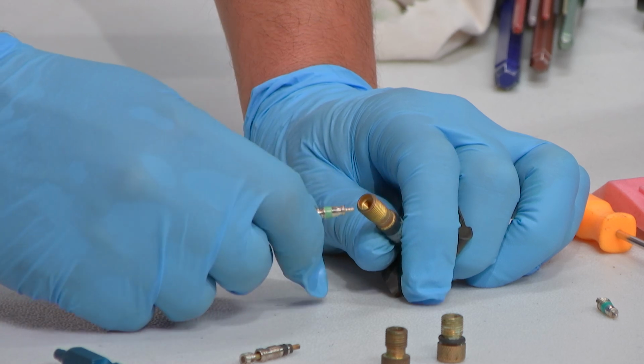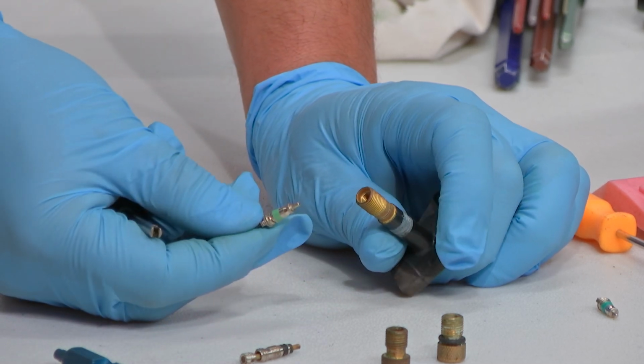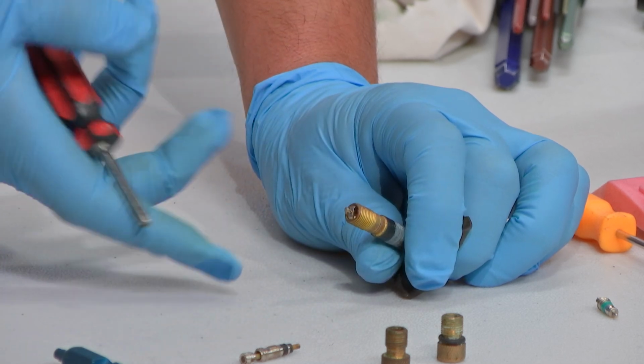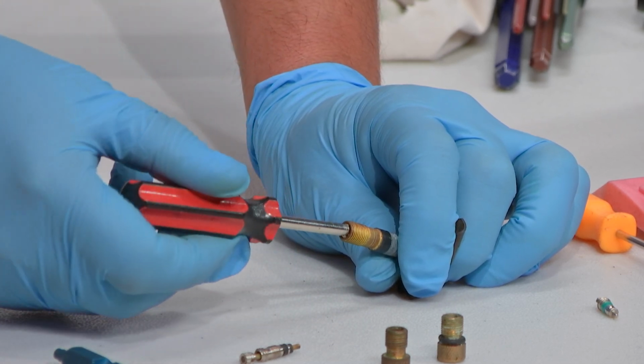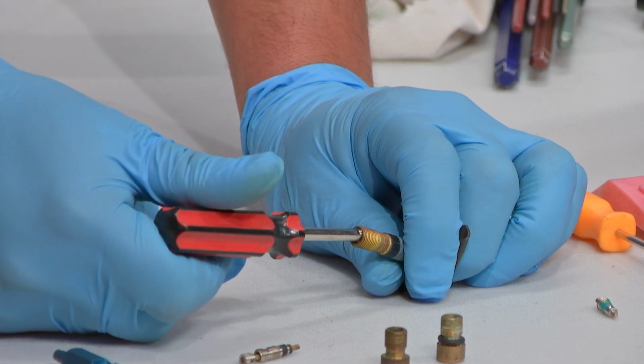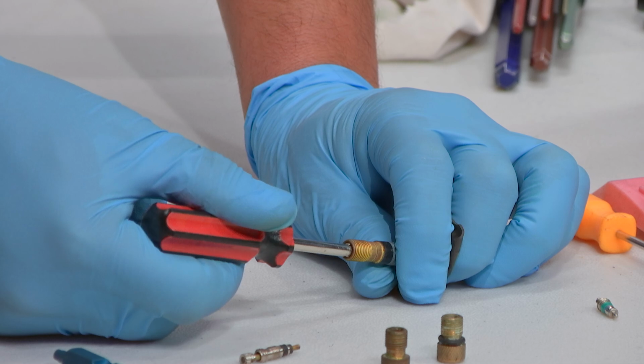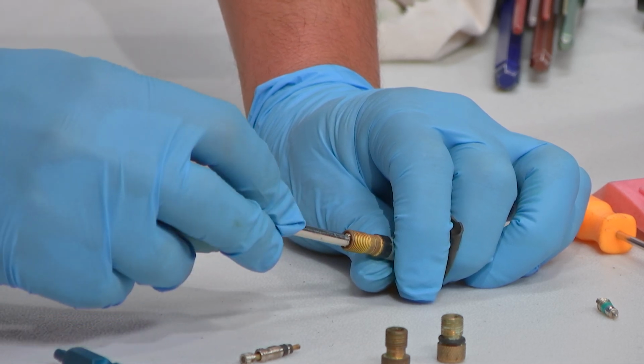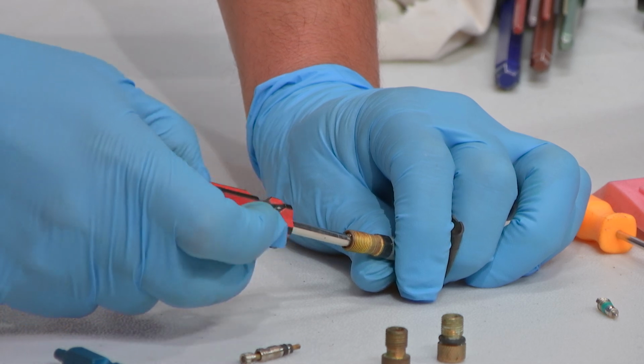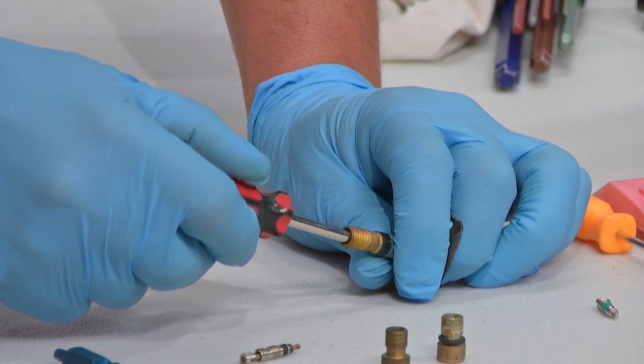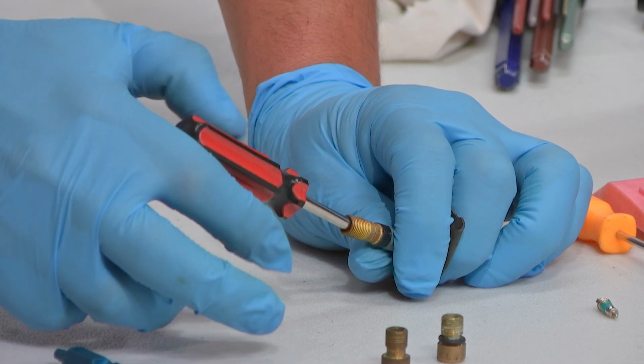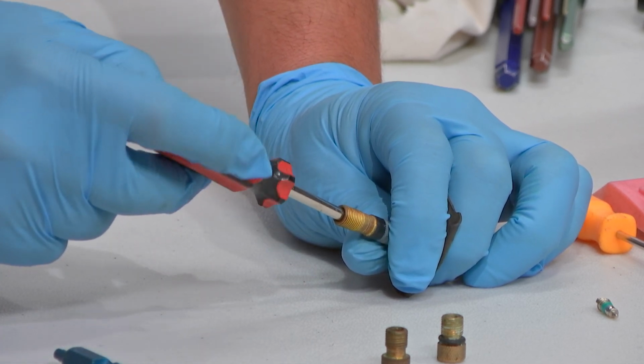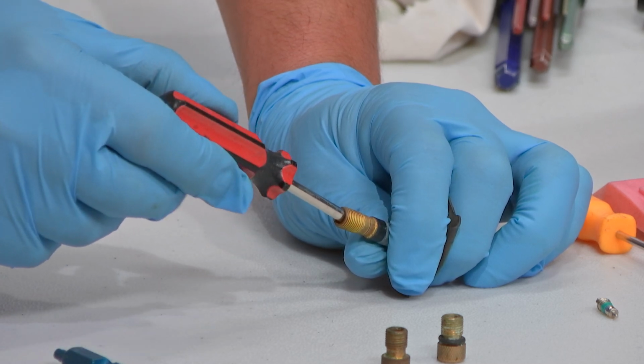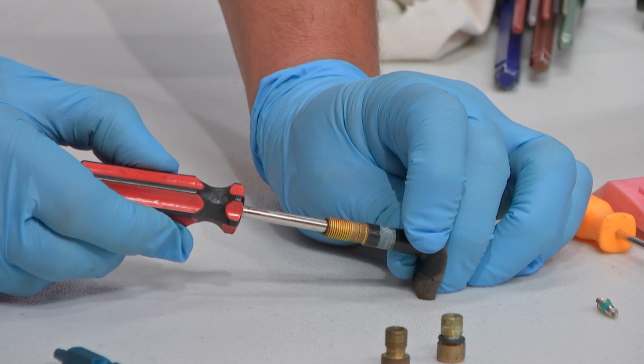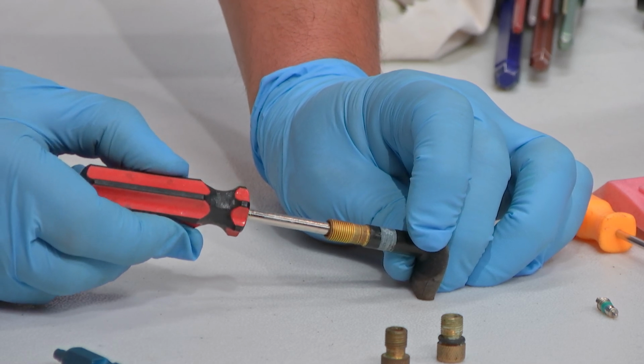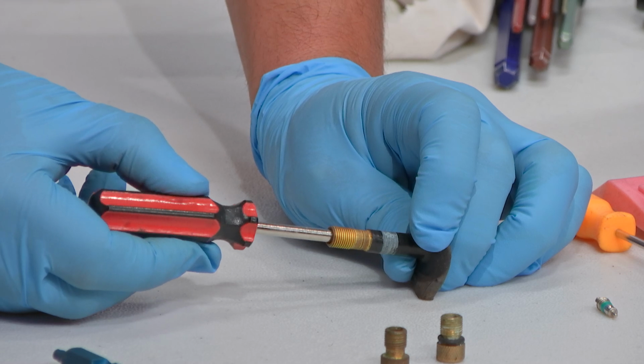To reinstall it, you just put the valve core back inside—I like to push it in a little. You're not going to use a lot of force since it's a very delicate valve. I turn it about one rotation to the left first so the threads seat properly, then turn it to the right, clockwise, to tighten, finger tightening with two fingers. Just like one Newton meter of force, not that hard.